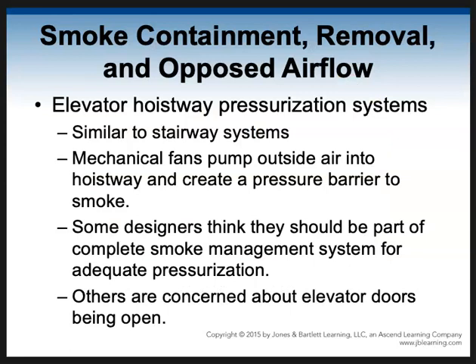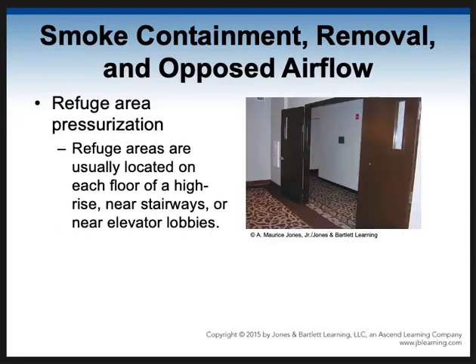Now, they also do similar kinds of systems in elevator hoistways. So it's very similar to the stairway systems where mechanical fans are going to pump outside air into the hoistway and create a pressure barrier, because if you think about it, the elevator hoistway is just like a chimney, and it'll take that smoke throughout the whole building. So some designers think they should be part of a complete smoke management system. Sometimes they're standalone, but there are others that are concerned about elevator doors being open. So elevators are automatically recalled to the bottom floor, so that hopefully won't happen.